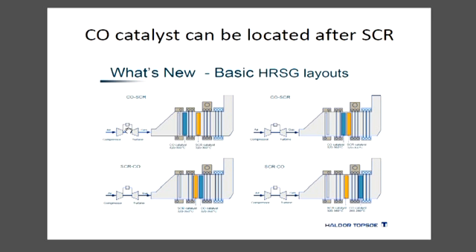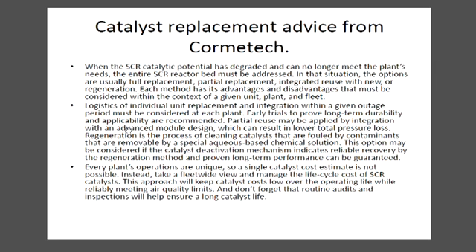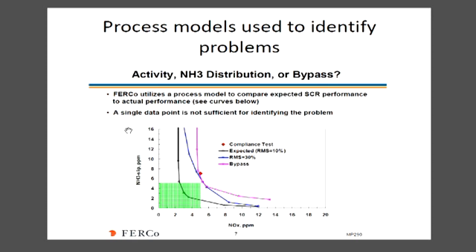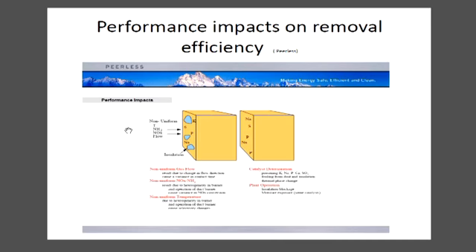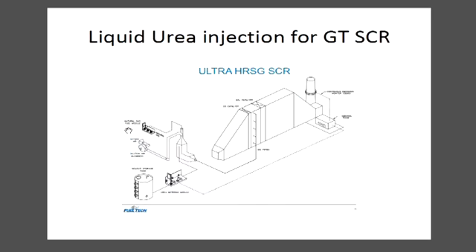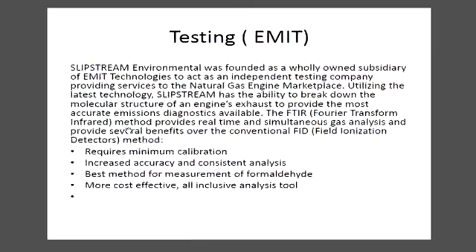We also covered the configurations of the various different honeycomb catalyst designs which are available. Companies like Haldor Topsoe are moving ahead with new catalyst designs — in fact they have a combination NOx and CO catalyst. AmeriChem is a major supplier with a number of different installations as well. Catalyst replacement is another consideration, though in gas turbines it's certainly less frequent than in coal-fired boilers. Ammonia distribution is another consideration, and CFD modeling is certainly advantageous if you're going to insert catalyst into an existing system.